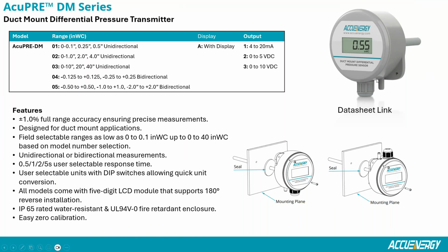This particular one, like I said, is designed for directly mounting to ductwork, so it has an integral probe already fastened to the enclosure. One thing nice about this one is you can rotate it if you want your wiring connections to come into the top or the bottom of the unit, so you can flip the LCD and mount it that way. It has a few user selectable features: pressure range, response time, and then your units of measurement. So if you're changing it to pascals or mmWC, you can change that with onboard dip switches.